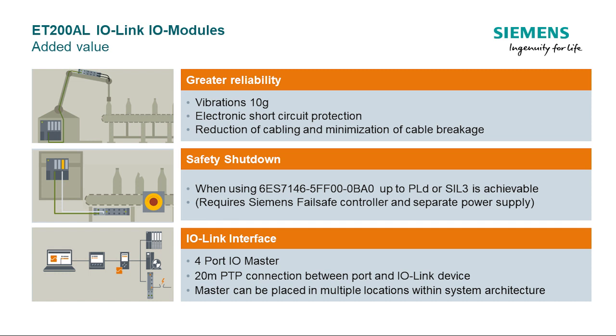Greater reliability with a vibration rating up to 10G makes it very suitable for robotic arm applications. Safety shutdown up to PLd or SIL 3 can be achieved by using the Siemens failsafe controller, failsafe module, and separate power supply. The I/O-Link four-port master can be directly attached to I/O-Link devices, including expansion modules up to 20m from the port.